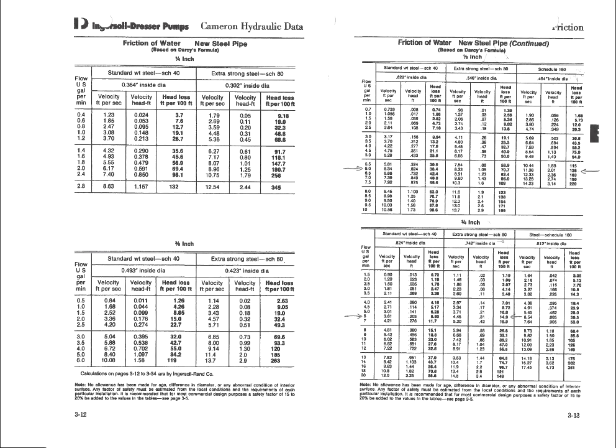If you look at the table for new steel pipe, half inch nominal pipe size, the closest we get to our 0.5 inch internal diameter is schedule 160, 0.464 inch internal diameter. Now I know you are not going to use schedule 160 pipe, but you will find polyethylene pipe somewhere that has an internal diameter close to 0.5 inches. If we follow along on the line for 6 gallons per minute and we go to the head loss feet per 100 feet, we get a value of 138. So we have 138 feet of head loss per 100 feet of pipe. In our case, for a 10 foot long pipe, this means 138 divided by 100 times 10 equals 13.8 feet of friction loss.